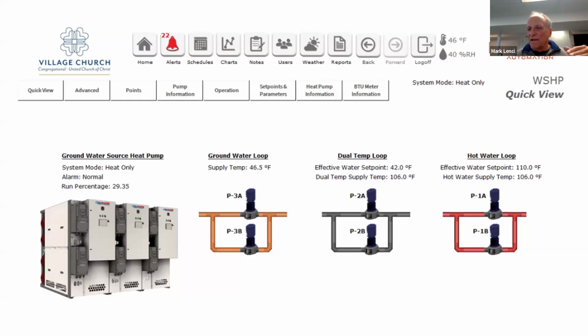But like we drop our sanctuary temperature down to 60 degrees Monday to Friday, right? Because we're not using it. To bring it back up to temp, then you kick, that's why you have this excess capacity here to bring yourself up to temp in a reasonable period of time. So this is what our calculation was, that we would need to not only heat at the hottest day and coldest day of the year, but to change that temperature as we bring those rooms online.